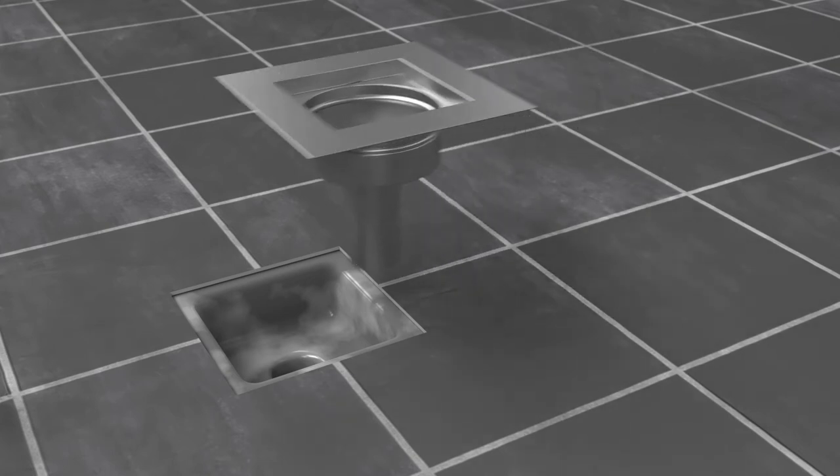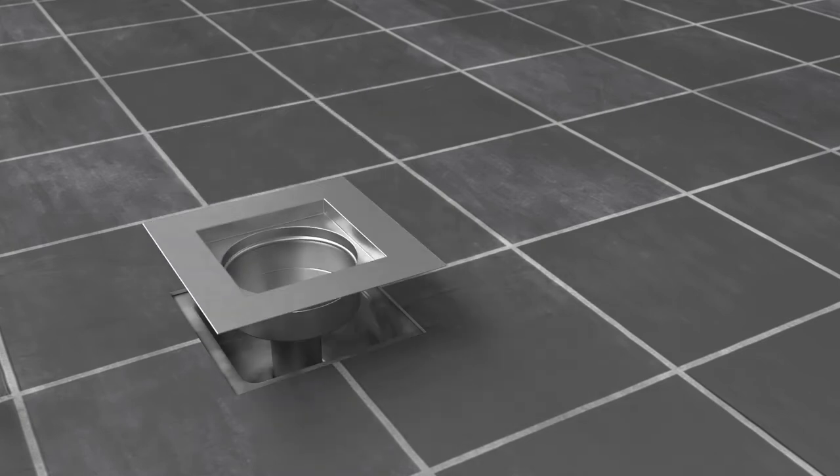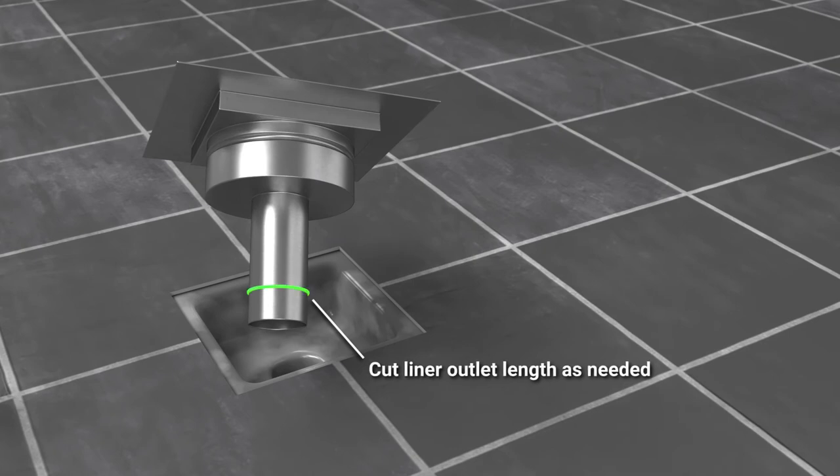First, confirm that the total height of the liner will fit into the existing floor sink or drain. Be sure the liner outlet does not bottom out on the installed drain pipe elbow or other restriction. Cut the liner outlet length as needed.